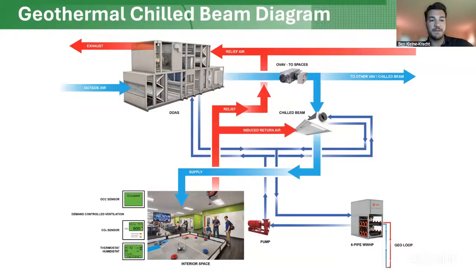And for this option, this is a 6-pipe water-to-water heat pump, which you're seeing on screen, and that is what would need the periodic maintenance. You would have 3 closed loop systems - a geothermal closed loop, a hot water closed loop, and a chilled water closed loop - that you would have to do quarterly or biannual chemical treatment on, just your typical closed loop hydronic system maintenance. And the chilled beam itself, there's not a lot of maintenance required - sometimes they have filters, sometimes they don't.